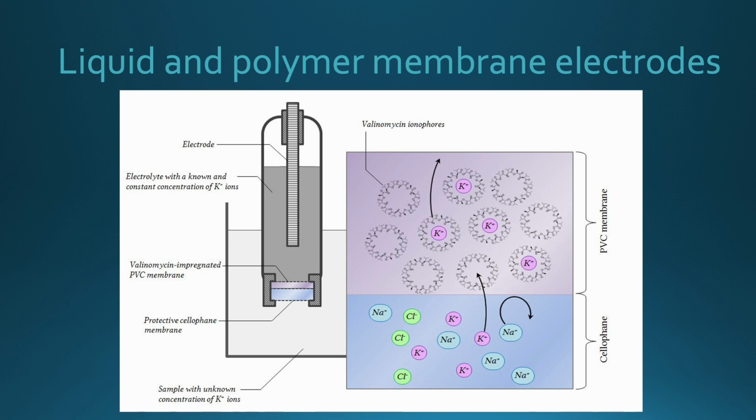Now, the commonest ionophore used is the one for potassium, and I'll show you in the next slide. But nowadays, different ionophores were developed to measure different analytes. This slide shows the classical potassium electrode, the potassium electrode that is used for measuring potassium in serum in most of the labs here in Kuwait. And it has, as you can see here, again, the internal reference electrode.